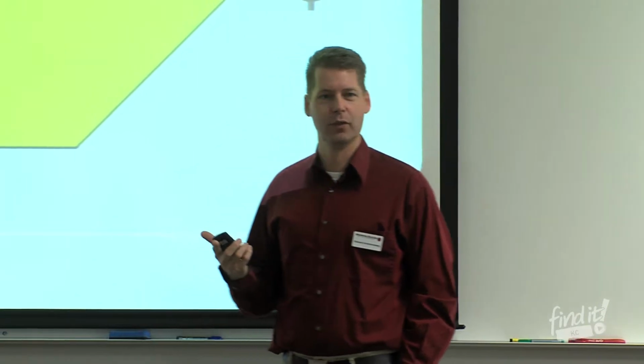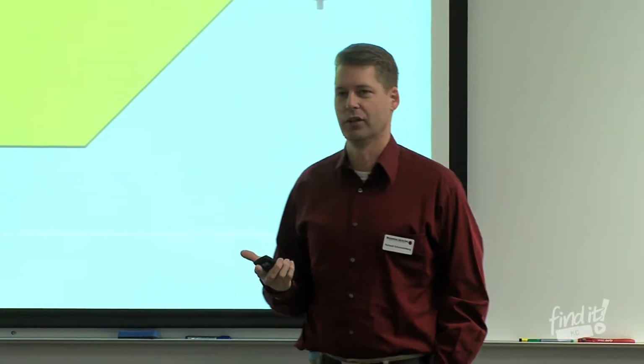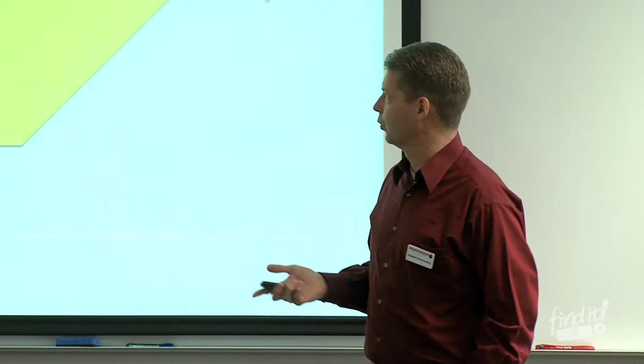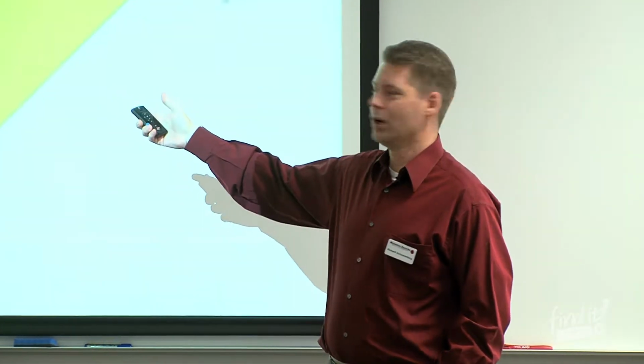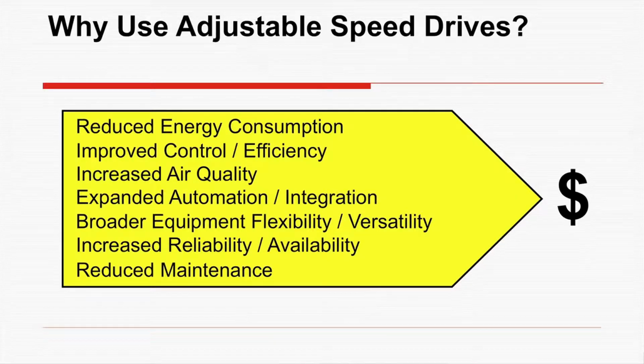Okay, so why do we use a VFD first and foremost? It's this magic black box that controls a motor speed, right? But why do we use it? It's one of those things that's become so common in the last 20 years, with how VFDs have proliferated in pretty much every motor on an HVAC system and other systems as well, that we kind of forget all the things it gives us. Primarily, it all comes down to money. We're doing it to save money, because we're reducing the maintenance and we're reducing the energy consumption of the drive. That's probably the big one. We're saving the energy by slowing the motors down. But there are all of these advantages that we can get on a VFD-driven system that we couldn't get if we were just across the line.